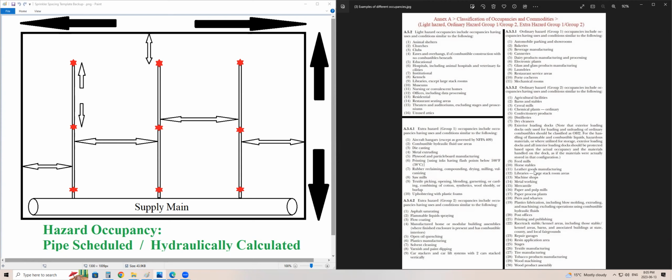However, typically the actual mall common walking area, the area in the middle of a mall, that's just a tile floor and you've got your escalators through there. That's typically considered a light hazard occupancy, because there are no commodities it's really protecting. It's just tile floor, maybe a couple of odd trees, a little bit of decoration. It's a lot of non-combustible construction, and not too many commodities being stored there.